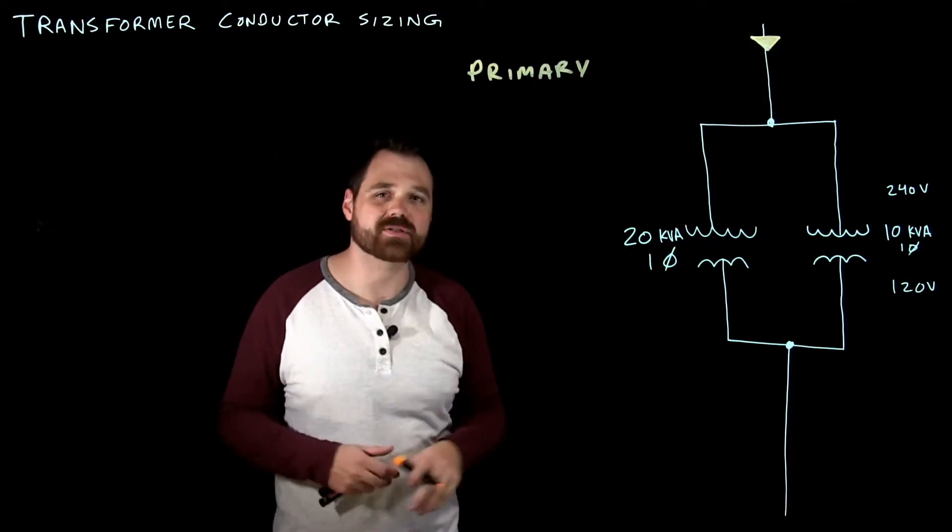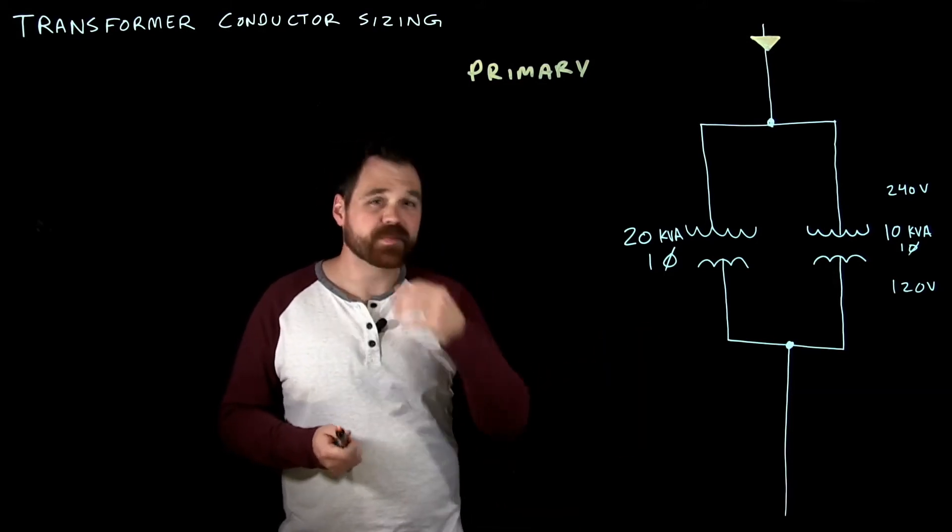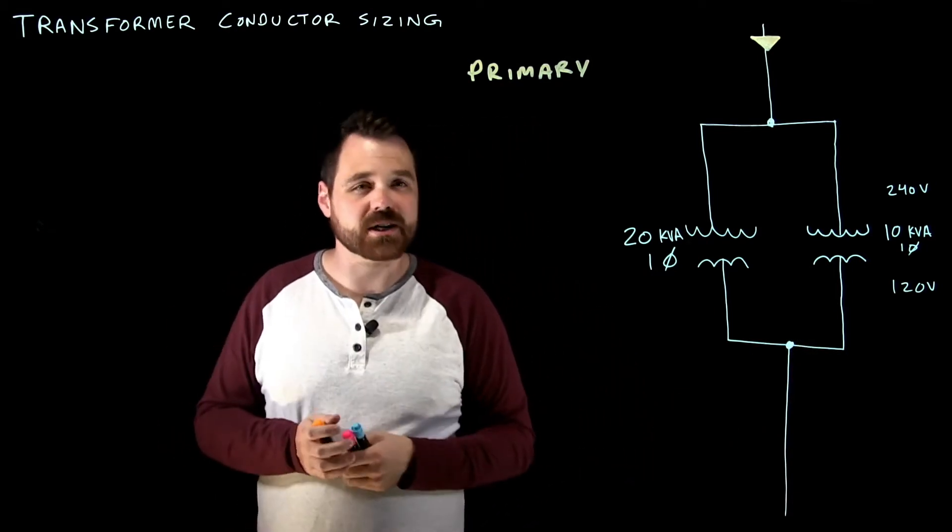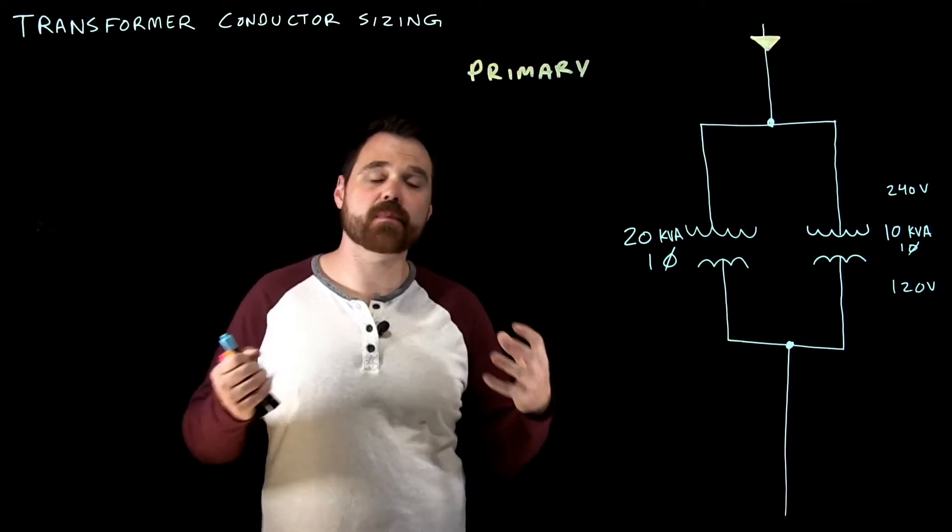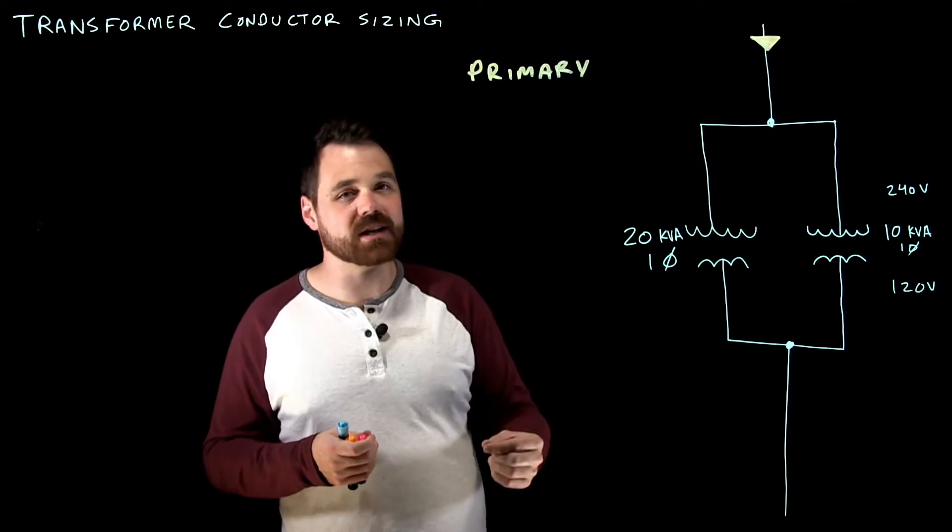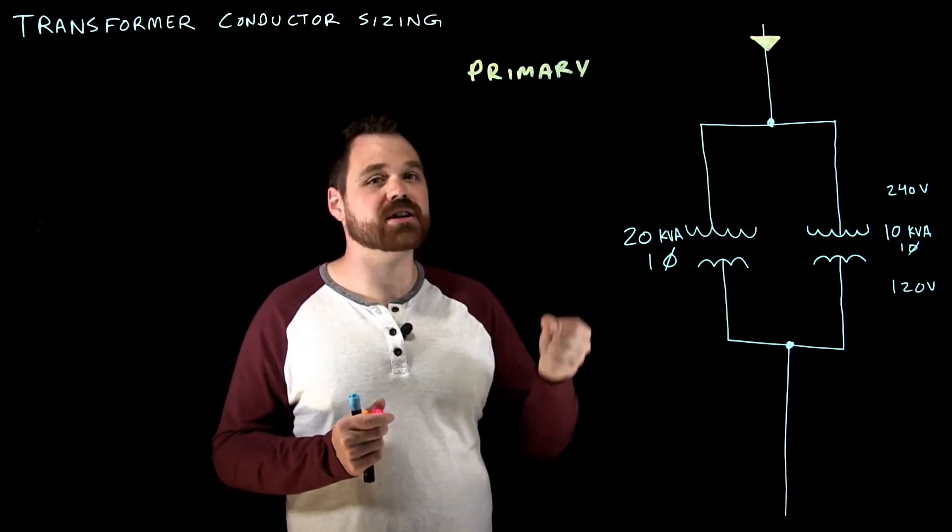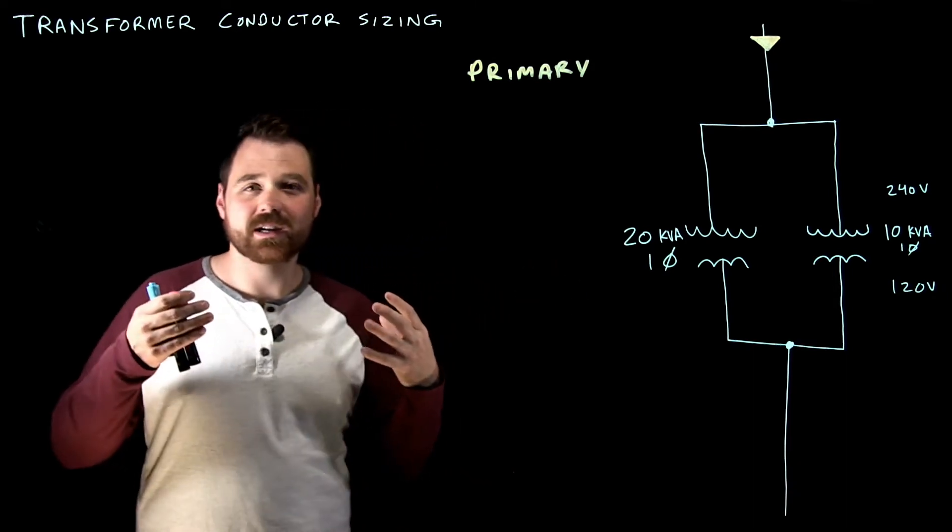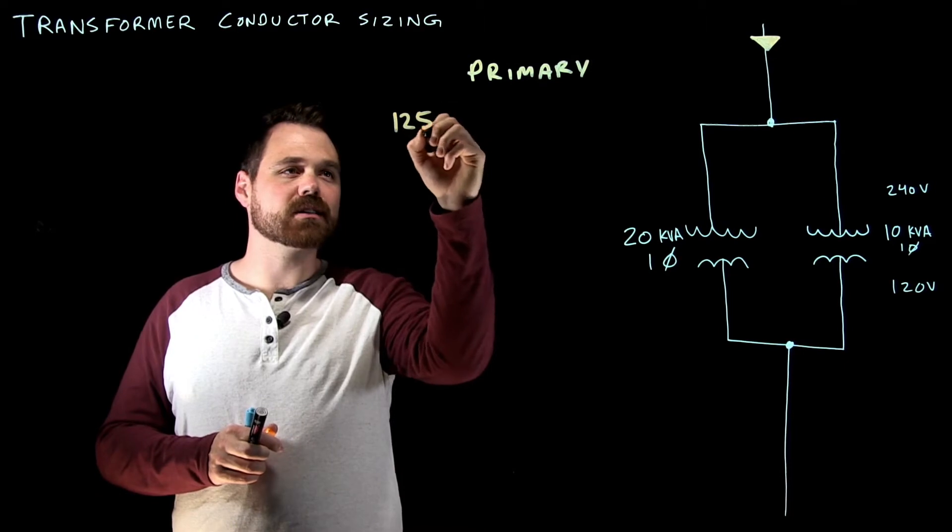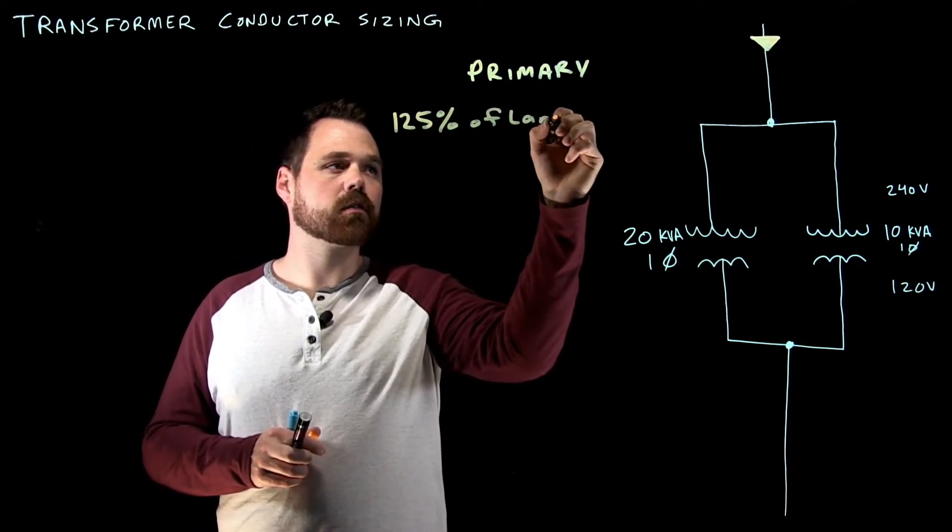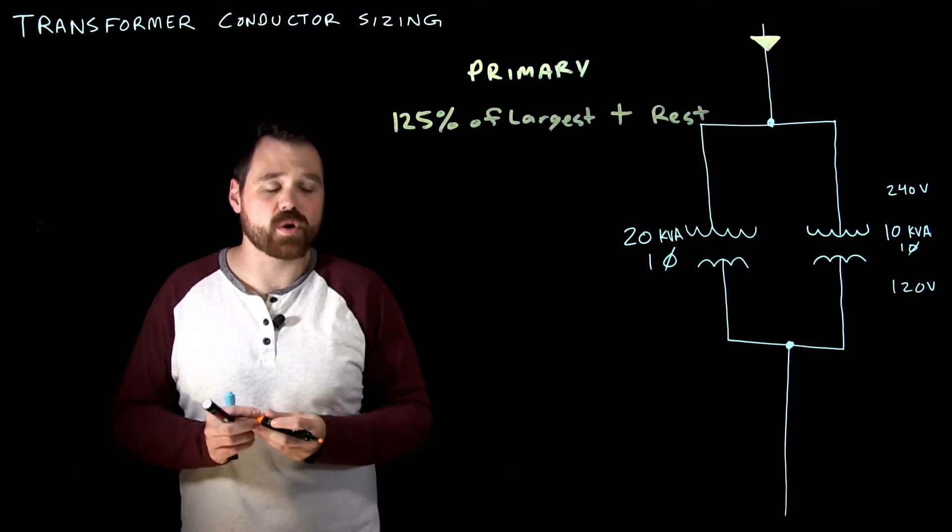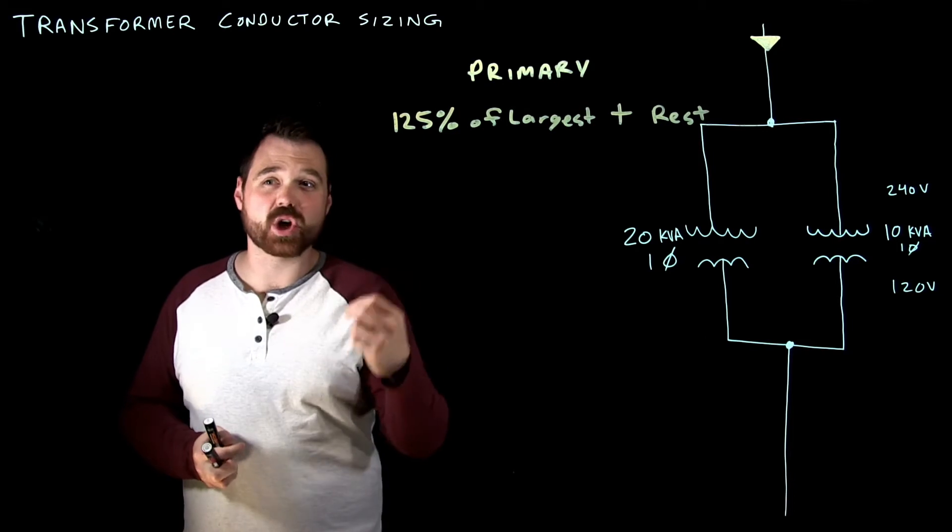Primary, so we're talking about sizing that bank of transformers. So what we're going to do is we're going to take a look in the rule, you'll notice now we're dealing with single phase transformers. So that's going to change our calculation a little bit. But what the rule tells me is when I'm feeding a bank of transformers, for the primary, it says the sum of all of the rated currents of the transformer, plus an additional 25% of the largest transformer. So I like to put that into one rule. And the way I read that rule or think about that rule, the way I do that calculation is I'm going to go 125% of the largest, plus the rest of them, or plus the remainder. Okay, so this is all based upon the rated current of the transformer.